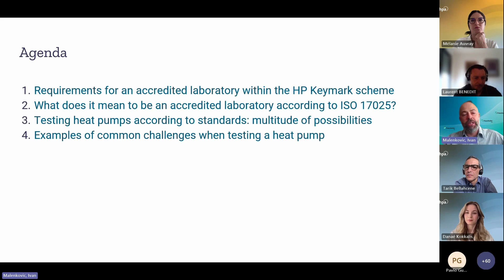So the first requirement to become a heat pump KEYMARK test lab is to have an accreditation according to ISO 17025. This is a third-party accreditation, as Tarik already said, and this is the main thing that you need as a test lab. After that, once you're accredited, you have to contact some of the empowered certification bodies. We saw there are 10 of them. You want to cooperate with them, and you have to get a positive assessment from them and sign a contract, which is then sent to the heat pump KEYMARK management. After they have accepted you as a test lab, you are listed with all your contact details, and this is publicly accessible on the Heat Pump KEYMARK website.